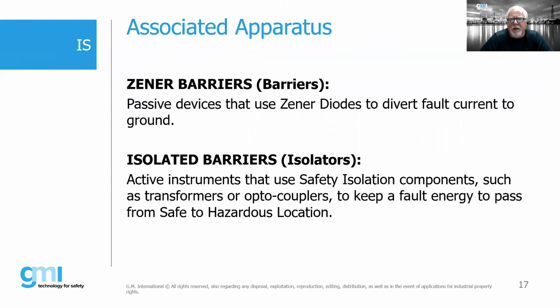So with our associated apparatus, there are basically 2 different designs, but they're both considered to be associated apparatus. One is the Zener barriers. We typically call these barriers. They're passive devices that use Zener diodes to divert any fault current to ground. The other concept is to use isolated barriers or isolators. These are active instruments that use some sort of safety isolation, typically a transformer or optocouplers, to keep fault energy from passing from a safe to a hazardous location. People use the terms barriers and isolators. Again, associated apparatus is the official term, if you will. Some people will call isolated barriers barriers as well, but basically Zener barriers and isolated barriers are the 2 main types of products that you'll find in the marketplace.